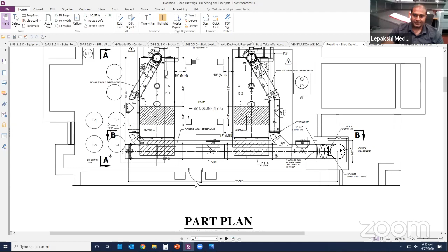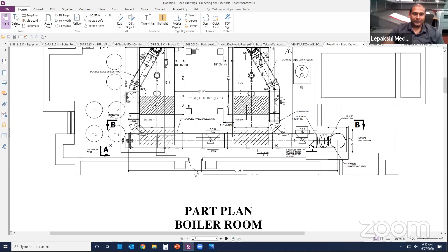At that time, you can't build a chimney like 200 feet high. It's going to stick out like crazy. How are you going to build that? What is the point? So the easiest way to resolve that sort of issue is to put a fan, an exhaust fan. It's called an induced draft fan or draft inducer. It induces draft. So what you're going to do, if, for instance, not in this case, you don't have enough draft available with this chimney, you'll put a draft inducer fan over here. What it does is it's going to suck all this stuff out and throw it outside. Pretty much that's it. It's that simple. But you have to make sure whatever the system that you are designing is doing what it is supposed to do. That's about the flue system.